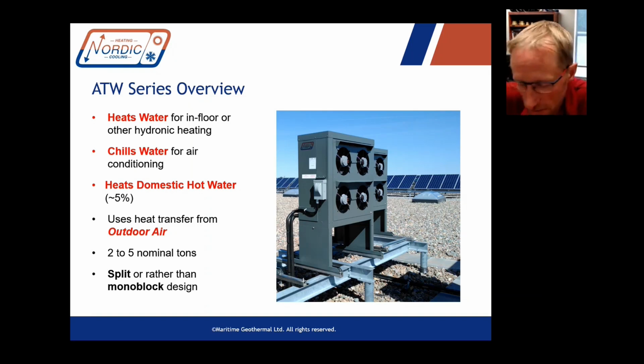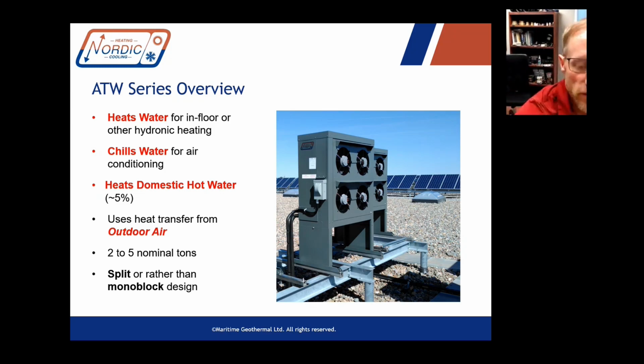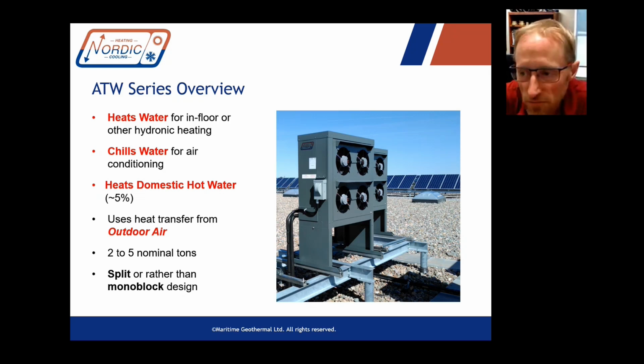Let's say your heat pump is running and there's no domestic water demand, it's going to heat that preheat tank right up to 140. And that's something that's good about the desuperheater feature, that it's not limited to the condensing temperature, because it's using a little bit of heat off the hot gas before that gas hits the condenser. So it can commonly heat the domestic water right up to the plumbing flow temperature of 60 degrees Celsius or 140 Fahrenheit, whereas the main output is limited to 105 to 120, which I'll mention in a bit. But it doesn't heat domestic water on domestic water demand. So you do need a final heating device to do the rest of the job, in case the desuperheater isn't running enough hours to give you all your hot water.